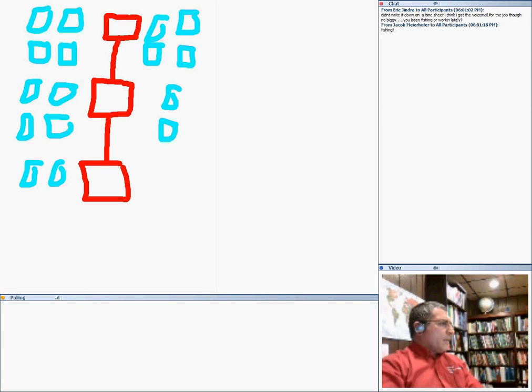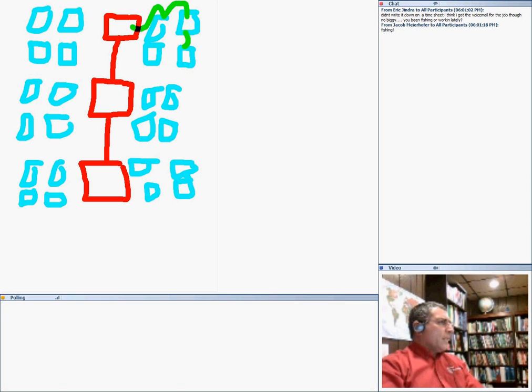So you can come out of here, and I drew a lot of fixtures here. Now you come over here out of this device. That will be a lot of fixtures to feed. So I can probably come from fixture 1 to fixture 2 to fixture 3 all the way. That's allowed in the code. And I can come also from here to here to here and all the way to here with an MC cable.